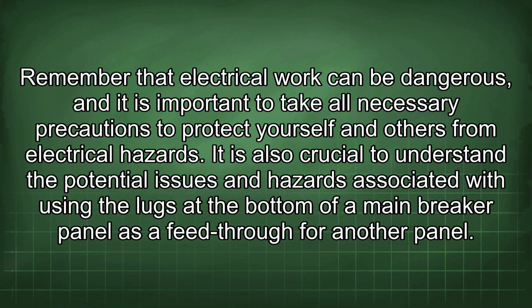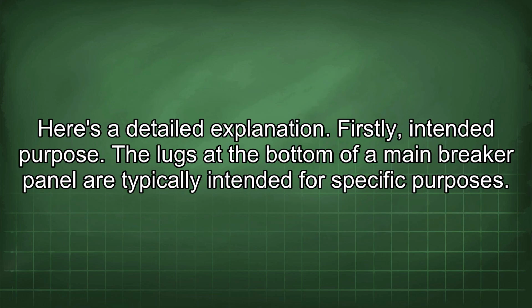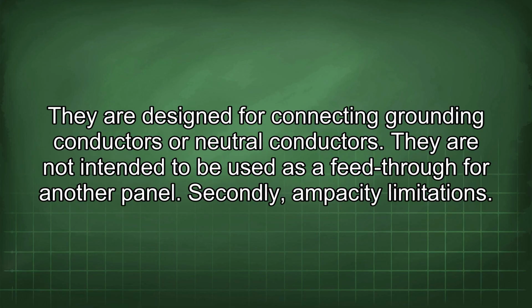Remember that electrical work can be dangerous, and it is important to take all necessary precautions to protect yourself and others from electrical hazards. It is also crucial to understand the potential issues and hazards associated with using the lugs at the bottom of a main breaker panel as a feed-through for another panel. Here's a detailed explanation. Firstly, intended purpose. The lugs at the bottom of a main breaker panel are typically intended for specific purposes. They are designed for connecting grounding conductors or neutral conductors. They are not intended to be used as a feed-through for another panel.